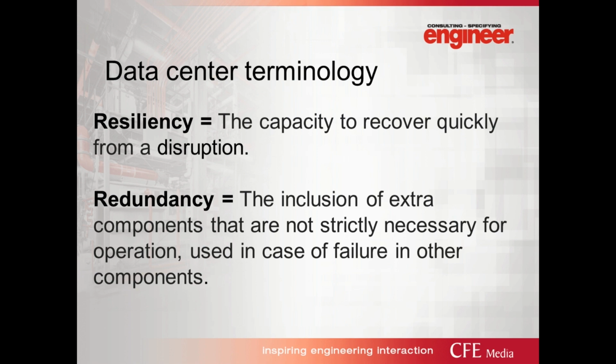Just saying N+1 or being N+1 on your components may not necessarily alleviate that issue. Based on your value set, OSHA, safety guidelines, these sorts of things, you can be N+1, still have plenty of single points of failure, and then you haven't met your goals.